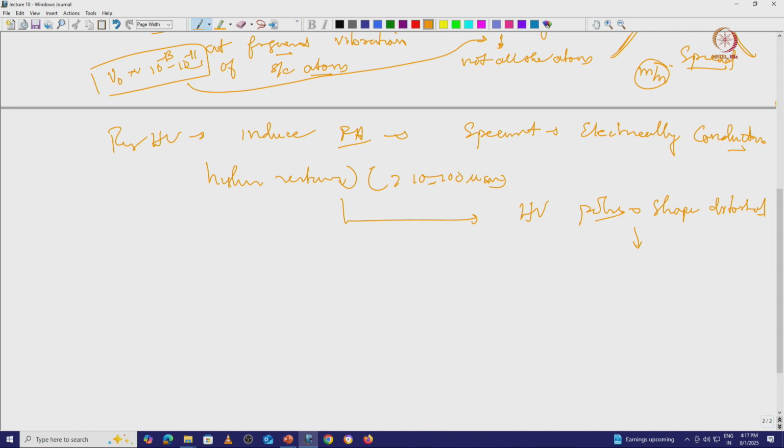This distortion can lead to a variation in the electric field with time, which distorts the timing resolution. So we cannot precisely measure the mass to charge ratio, and it will directly affect the mass resolution if the material has a very high electrical resistivity.